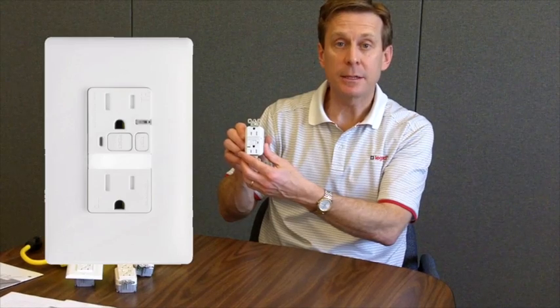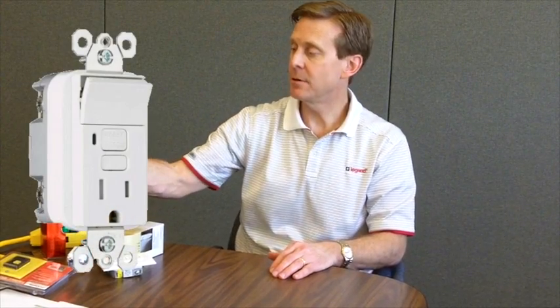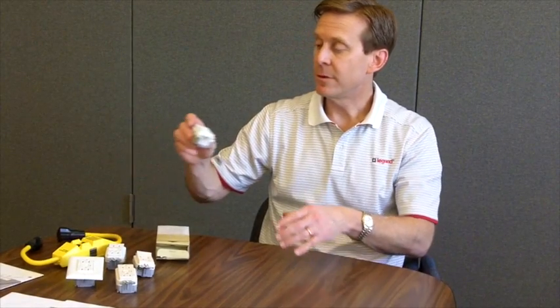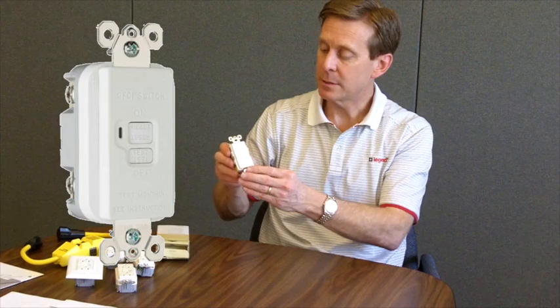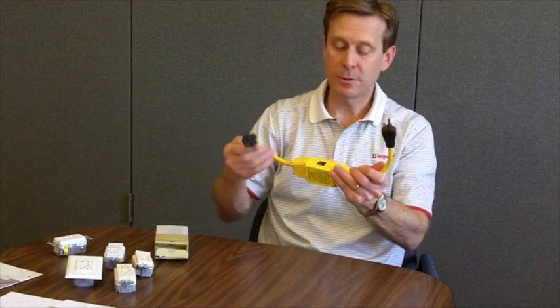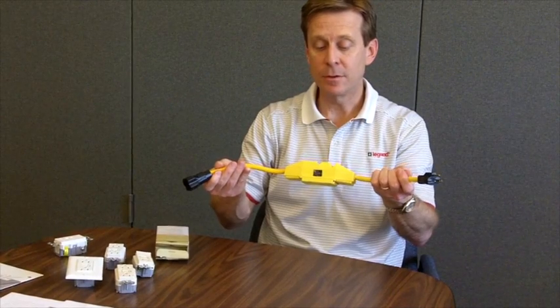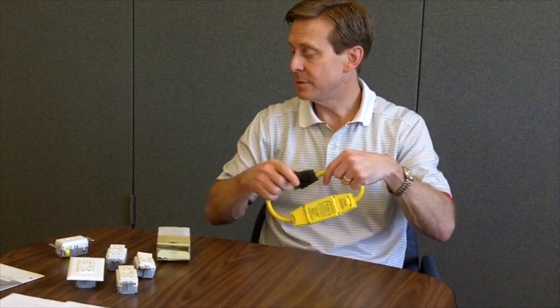There are GFCIs with built-in LED night lights rated for 20-year life. There are switched GFCIs, very useful for remodel work where you have a single gang electrical box and want to add a switch to an outlet. Dead front GFCIs have no receptacle or outlet blade openings — they're used to protect a spa or hot tub wired downstream. Portable GFCIs are also very useful — basically a cord set or extension cord with built-in GFCI protection for use when plugging into an outlet that doesn't have its own GFCI protection.